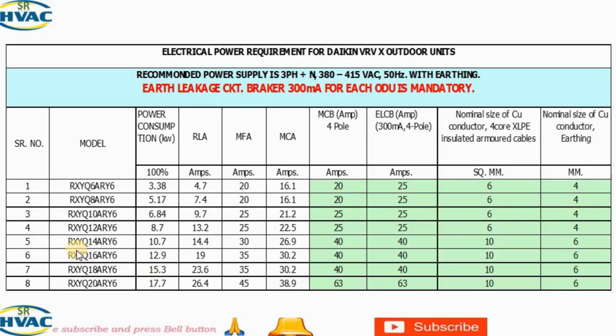We have an increase from RXYQ 14 HP ARY6. This is the 14 HP. The load will be 10.7 kilowatt. Okay friends, and this is the 40. You need the MCB of 40 ampere. You need the ELCB of 40 ampere. You need the cable size of 10 square mm for power cable, and the earthing will be 6 mm.